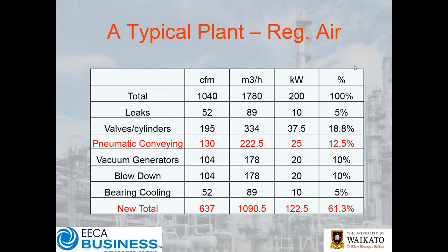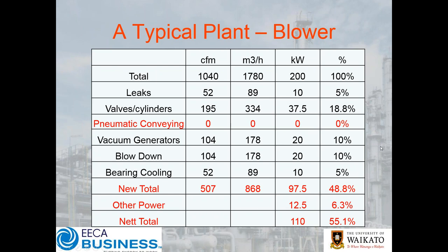Going back to our typical plant: assuming we've just regulated the air down, our pneumatic conveying has dropped in half and we're now down to 61% overall. Alternatively, if we throw a blower in, pneumatic conveying in terms of compressed air drops to zero. We've introduced replacement other power — our blower system — displacing 12.5% with only 6.25%, and even with the extra blower we're sitting at 55%. Substantial savings are starting to stack up.